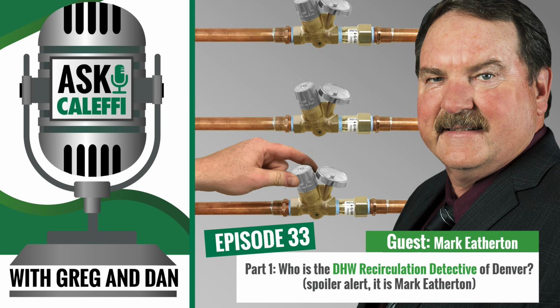And once you determine how to look at this stuff and how to test for it, then you can eliminate it. There's probably 2 or 3 different types of cartridge valves on the market that have an issue. Moen is one, and Moen has admitted to it openly. They were giving away cartridges for a long time trying to take care of this issue. Okay. I can't remember the names of the other ones, but they're older. Most of the new systems that are installed have check valves on both the cold and hot supply going into the valves, so it eliminates any possibility of cross connection. Cross connection could still occur, but it's not going to allow any backflow or cross feeding from cold into the hot water mains themselves. So the problem has pretty well been negated in any newer systems.